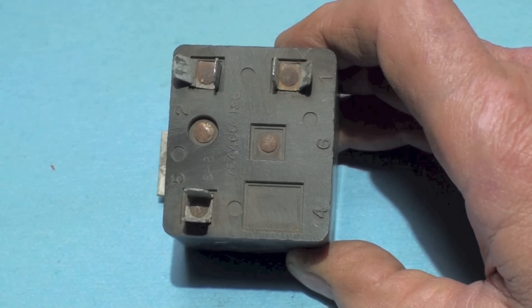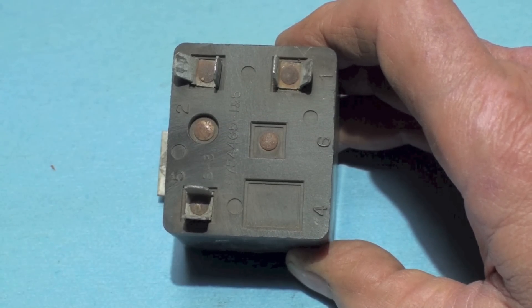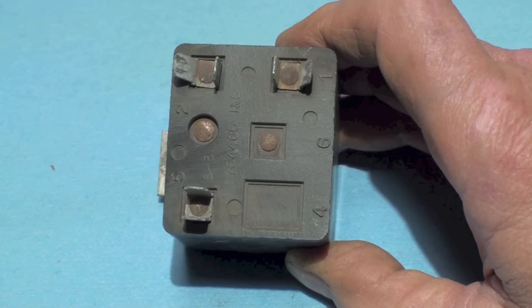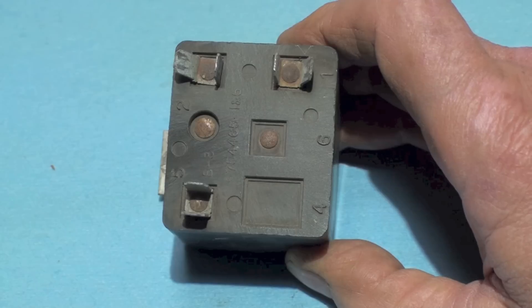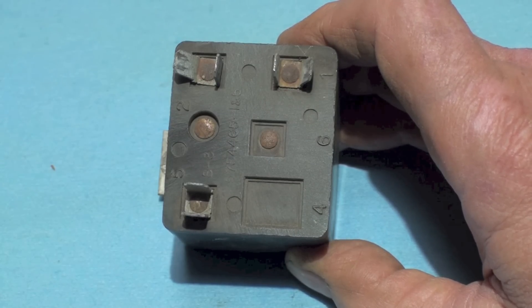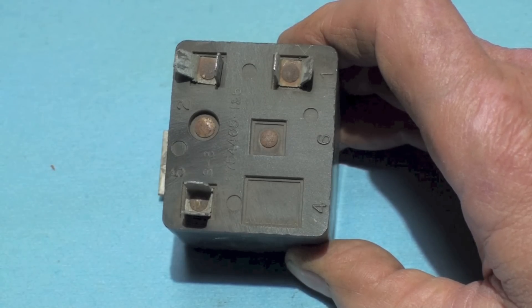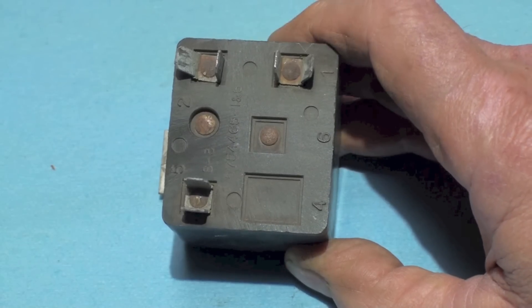Now these are usually used on PSC motors, permanent split capacitors. It's actually going to be a capacitor start capacitor run motor, so it's got a large capacitor placed in the start circuit through this relay to energize the start winding.